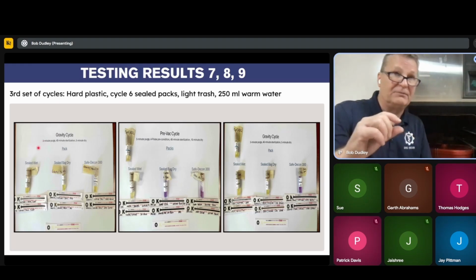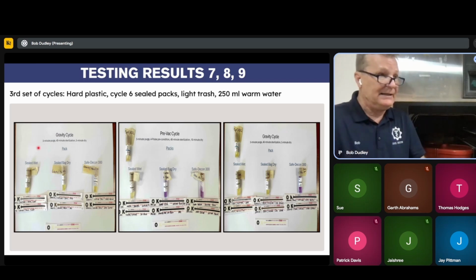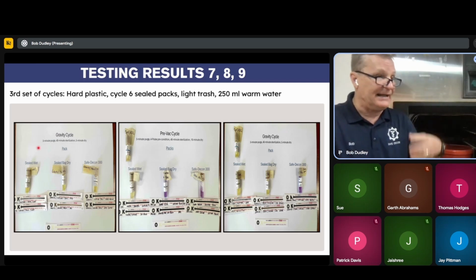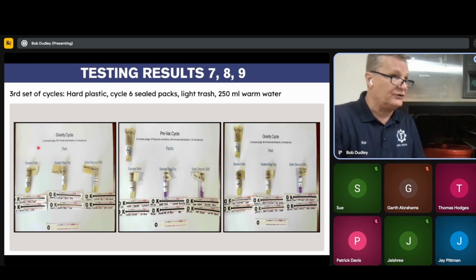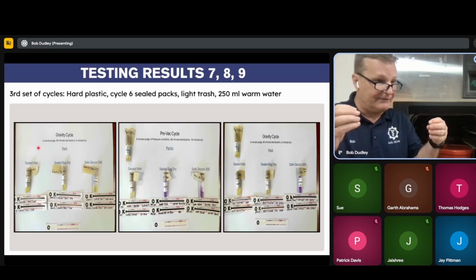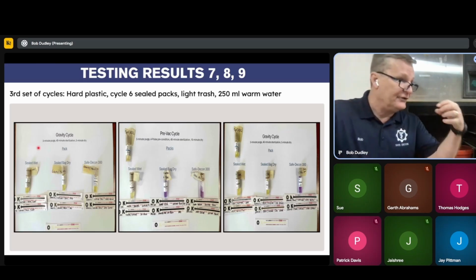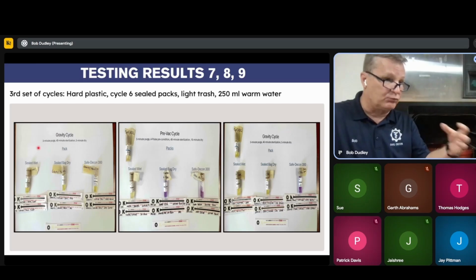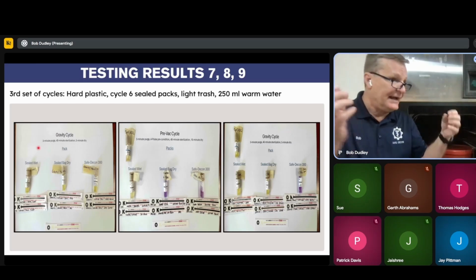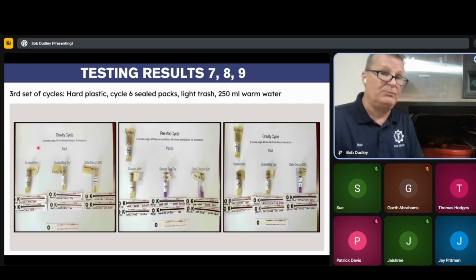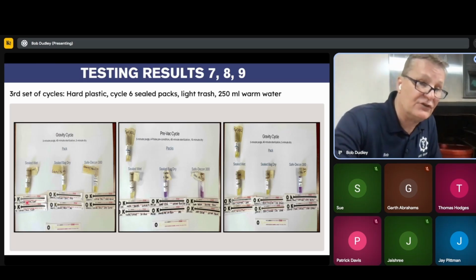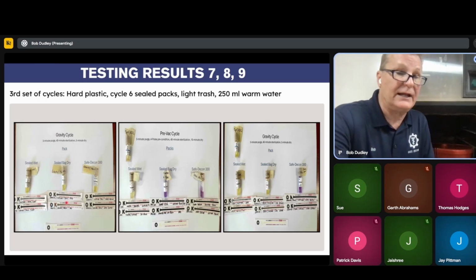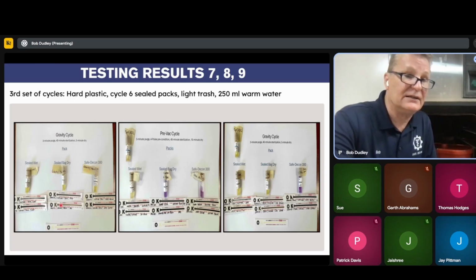So when you have something dense that you're trying to get heat into, it's going to have a hard time penetrating. The gravity cycle is just going to push so far. It's going to develop literally a ring of liquid around it, and it will not allow that heat to be pulled out. And what happens is, as you can see by your chemical strip, it's saying, well, yeah, I did achieve temperature here, but it's not long enough to get the kill.